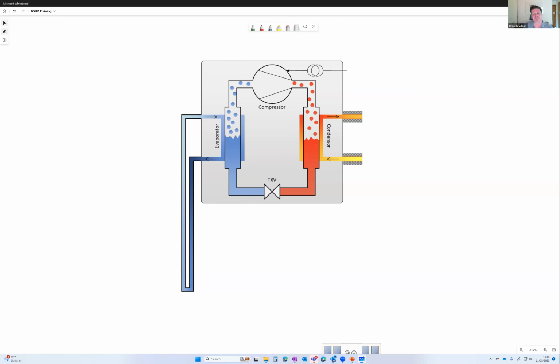Very simply, it manipulates the pressure in a gas-liquid cycle to allow the liquid to evaporate into a gas at low temperature, picking up heat, and condense at high temperature, dropping that heat back off. It manipulates that pressure using the compressor up here, which runs on electrical energy. There's a final part to the system, the thermal expansion valve down here, which moderates and controls the refrigeration cycle to keep it in the window where it's most efficient and delivering the temperatures you want. It's actually a small pinhole that opens and closes in response to what's going on in the refrigeration circuit. So that's a high-level, quick overview of how a heat pump works.